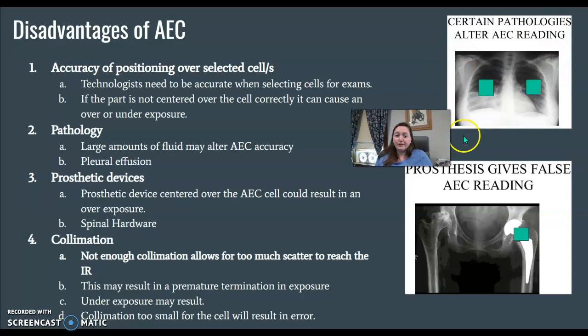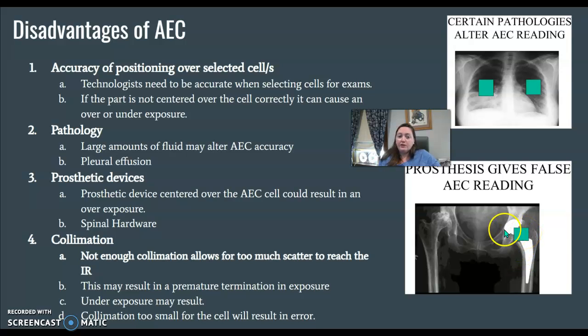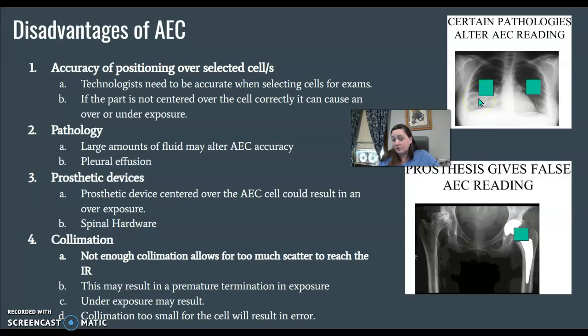Disadvantages. AEC is wonderful, but it's not a magical unicorn. You have to use it properly or set up your settings properly for it to actually help you. We already talked about accuracy of positioning of the cells, choosing the correct cell, and putting the part over the cell. Other things that could cause an error with AEC include prosthetic devices, like hip replacements or spinal hardware. If we know these are present, we need to be aware of our chamber selection or set a manual technique. It could also be pathology — large amounts of fluid, like pleural effusion, can affect AEC accuracy. If most of the lungs are filled with fluid and we're placing those cells too low into the fluid, that will change our accuracy with exposures.